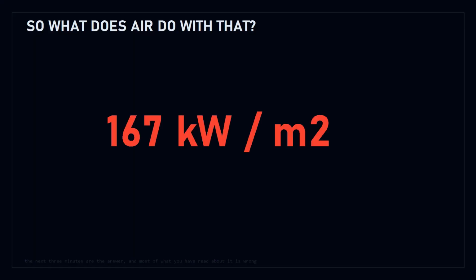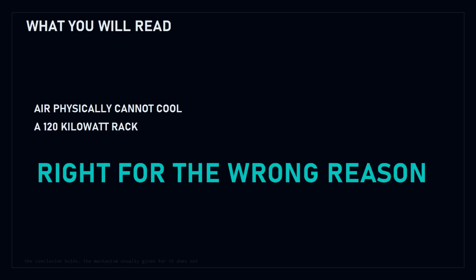167 kilowatts per square meter. What does air actually do with that? You will read constantly that air physically cannot cool a 120 kilowatt rack. That turns out to be right for the wrong reason. And the right reason is more interesting.